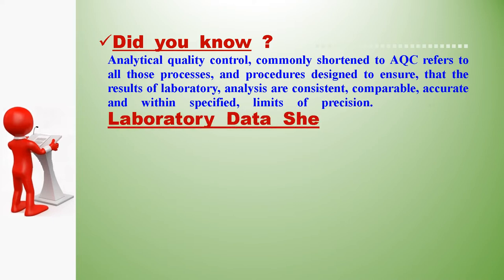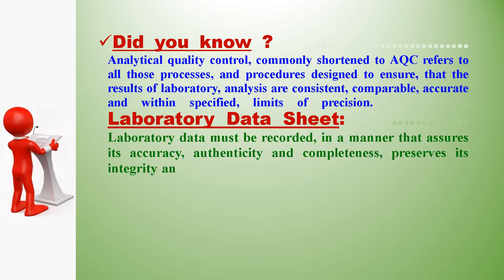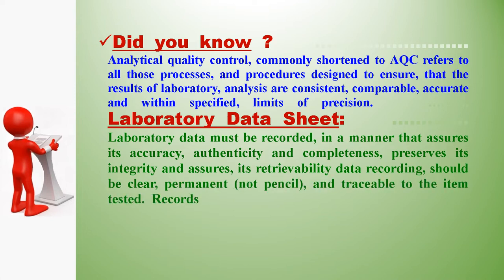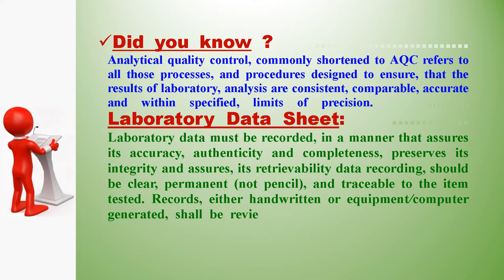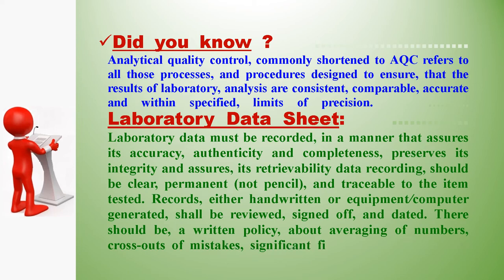Laboratory data must be recorded in a manner that assures accuracy, authenticity, and completeness, preserves its integrity, and assures retrievability. Data recording should be clear, permanent (not in pencil), and traceable to the item tested. Records, whether handwritten or equipment/computer-generated, shall be reviewed, signed off, and dated. There should be a written policy addressing averaging of numbers, cross-outs of mistakes, significant figures, and leaving notebook pages or fill-in-the-blank entries empty.